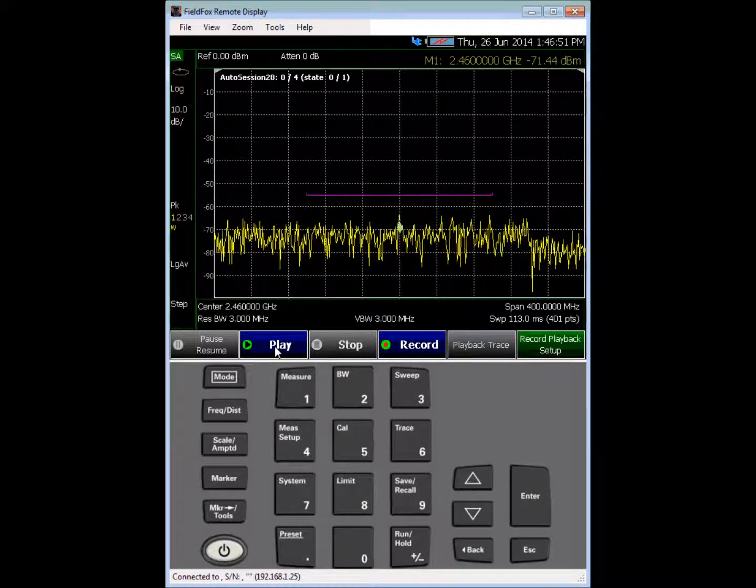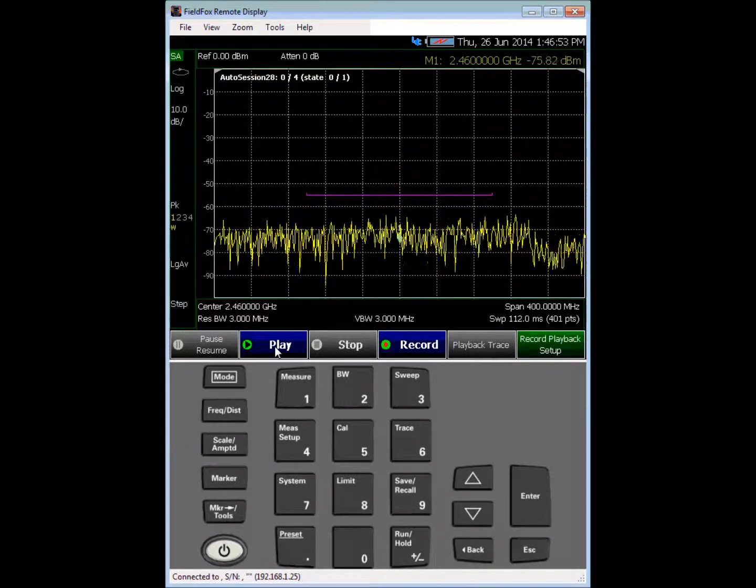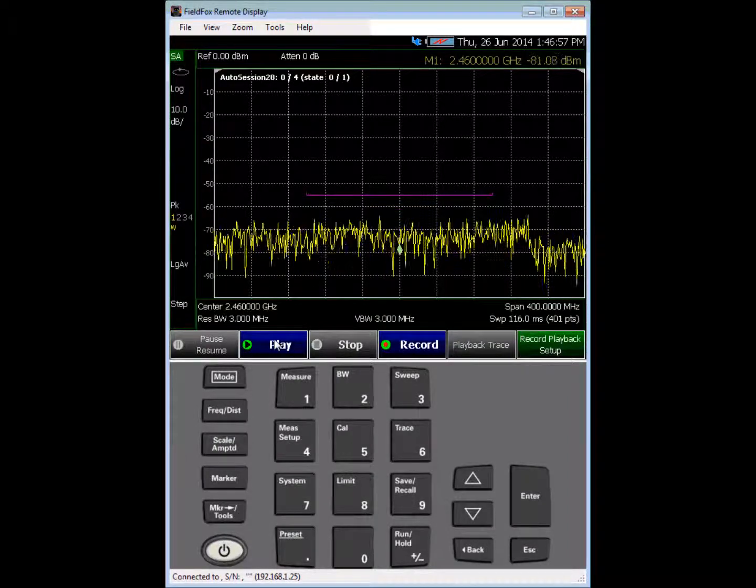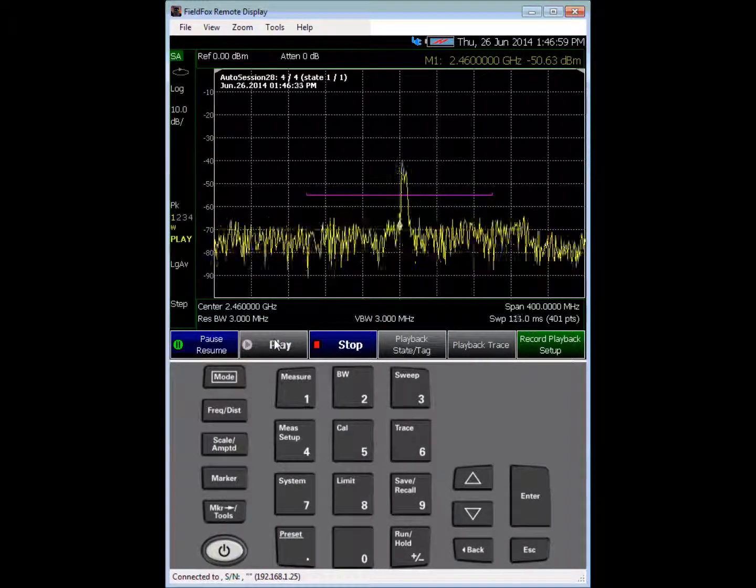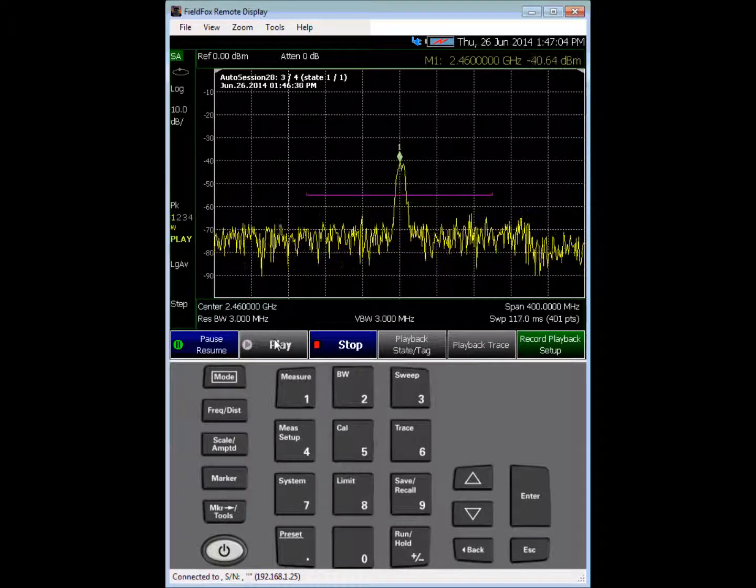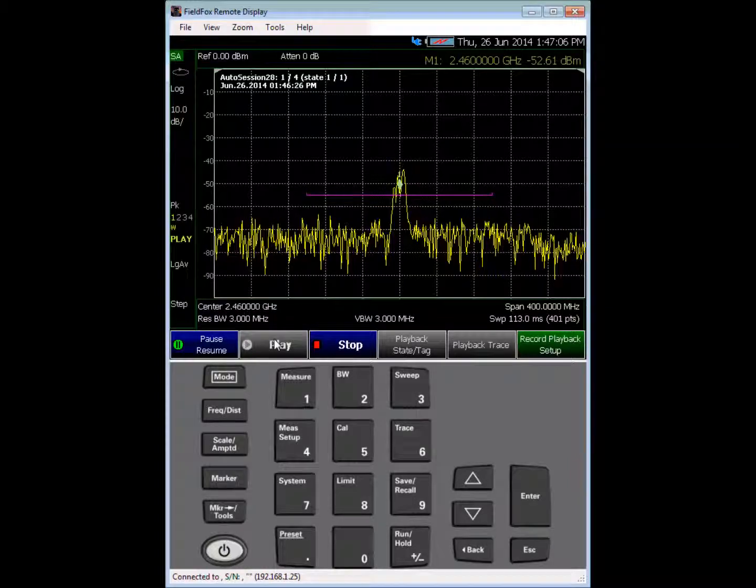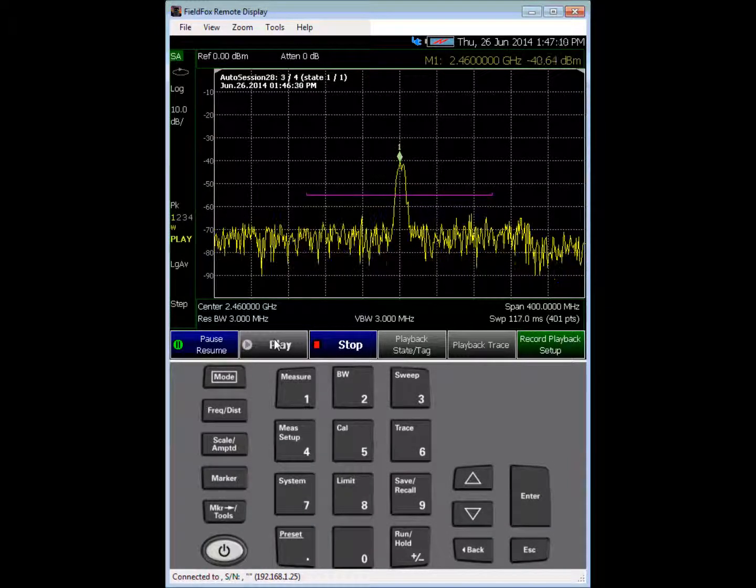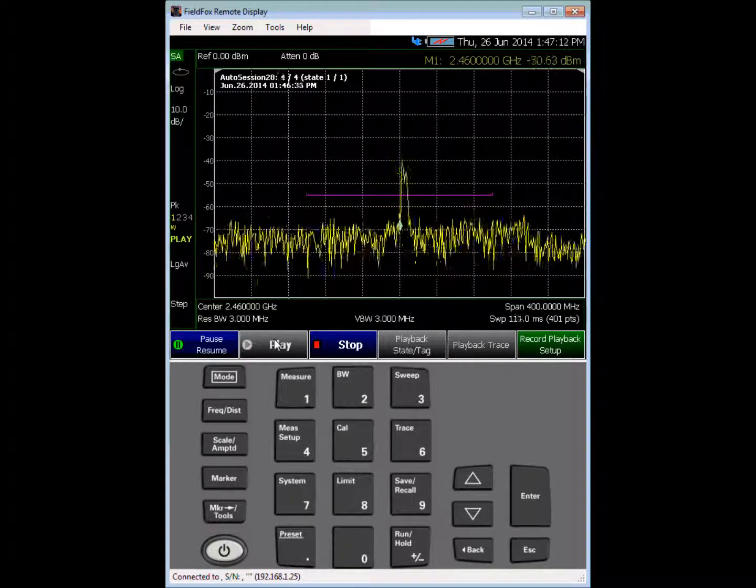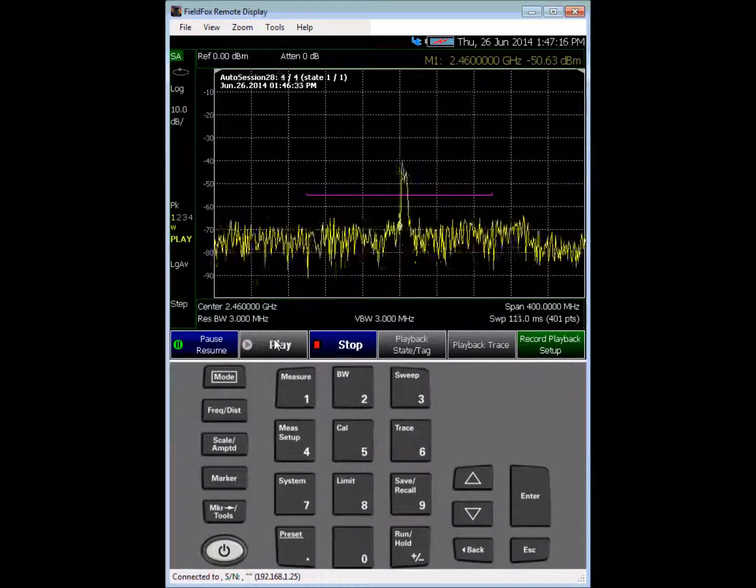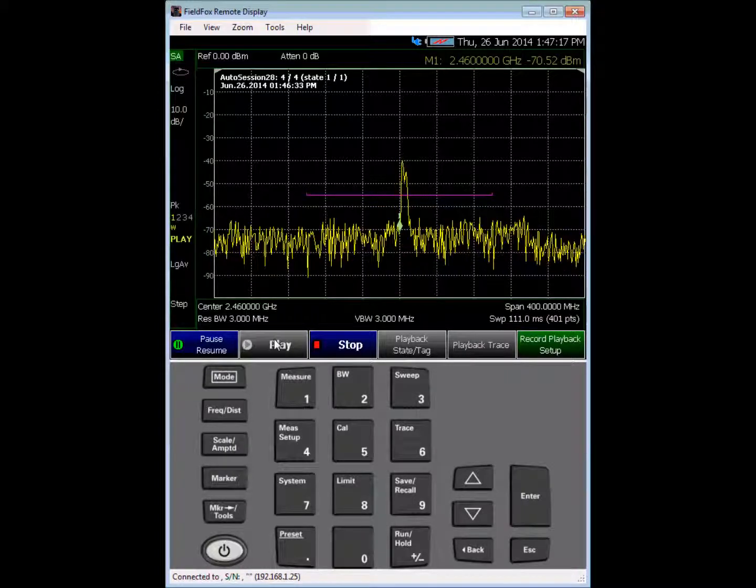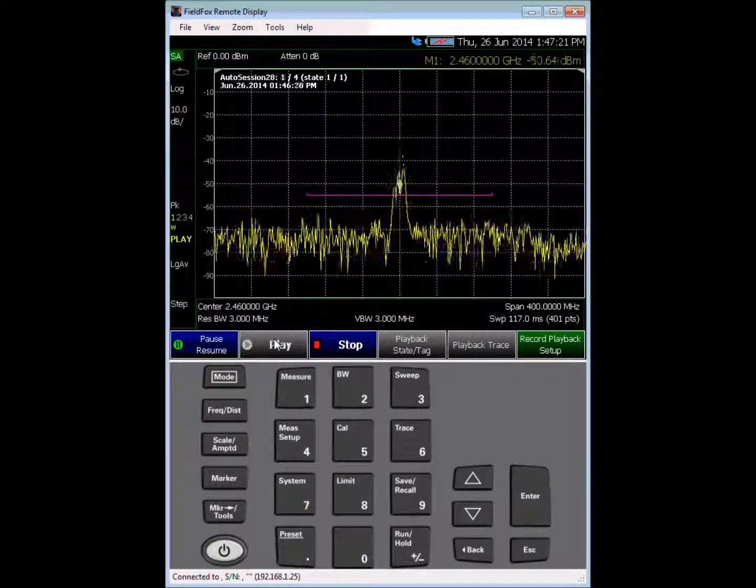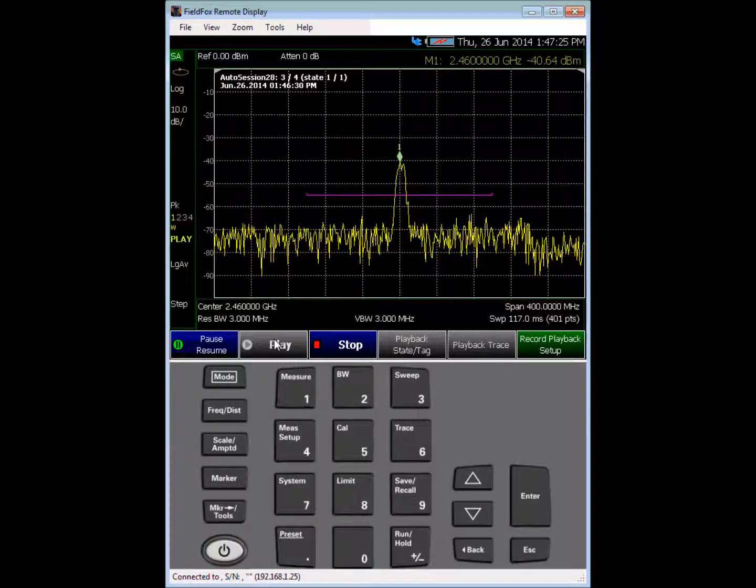And I want to play back the recording. Now what I hope to see in this recording when I play it back is only those times that the signal exceeded the limit. And so here we have it, so we're only seeing the signals and recording a long period of time. This could be days where the only recording that occurs is when you exceed the limit. So here's the playback. Notice it's going into a loop, so you're just going to see this over and over. Okay, I hope this has been helpful. You have a great day.